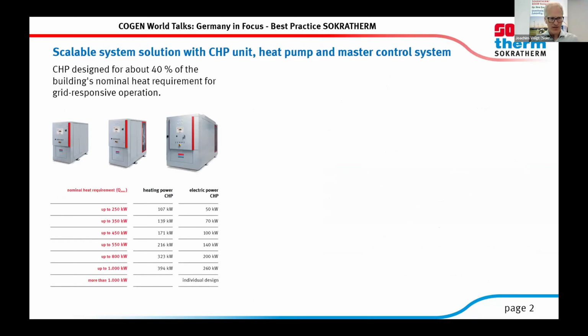And from these considerations, we developed a scalable system solution with a CHP unit, heat pump, and a master control system for intelligent operation of the whole plant. So the CHP will be designed a bit bigger than in recent years, with about 40% of the building's nominal heat requirement, to be able to serve a grid-responsive operation and to help the electricity market with covering residual load.